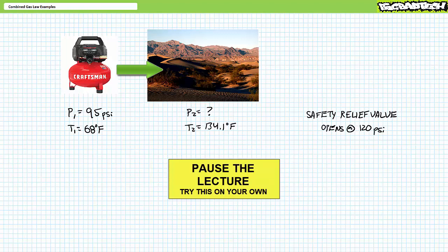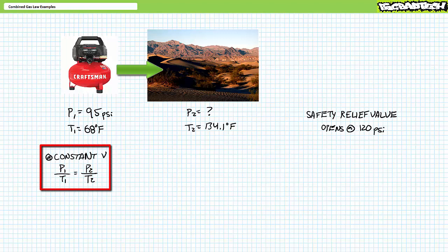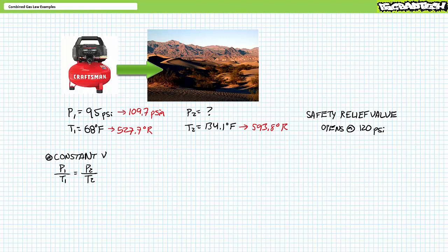This scenario calls for application of Gay-Lussac's law. Given constant volume, pressure and temperature are related as P1 over T1 equals P2 over T2. Given increased temperature at the job site, pressure in the receiver will undoubtedly rise. First, convert the two temperatures to the Rankine scale and convert gauge pressure to absolute. 95 psi gauge is roughly equivalent to 109.7 psi absolute. 68 degrees Fahrenheit is equivalent to 527.7 degrees Rankine. And 134.1 degrees Fahrenheit is equivalent to 593.8 degrees Rankine.